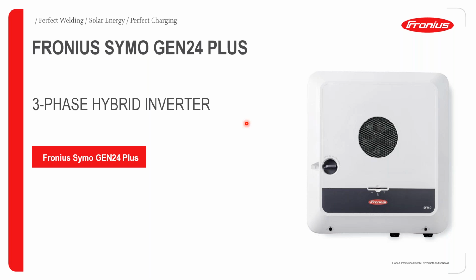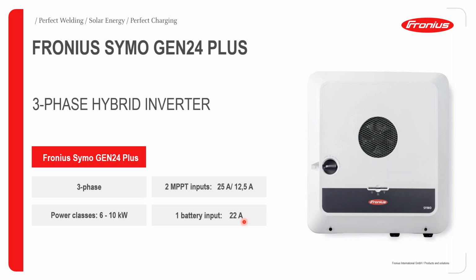We do have the 3-phase inverter, or what we refer to as the Symo Gen 24. It comes with 2 MPPT inputs. 1 MPPT has a higher power handling capacity of about 25 amps, and the next MPPT can handle up to 12.5 amps. Power classes for the 3-phase Symo Gen 24 Plus range from 6 kilowatts to 10 kilowatts.